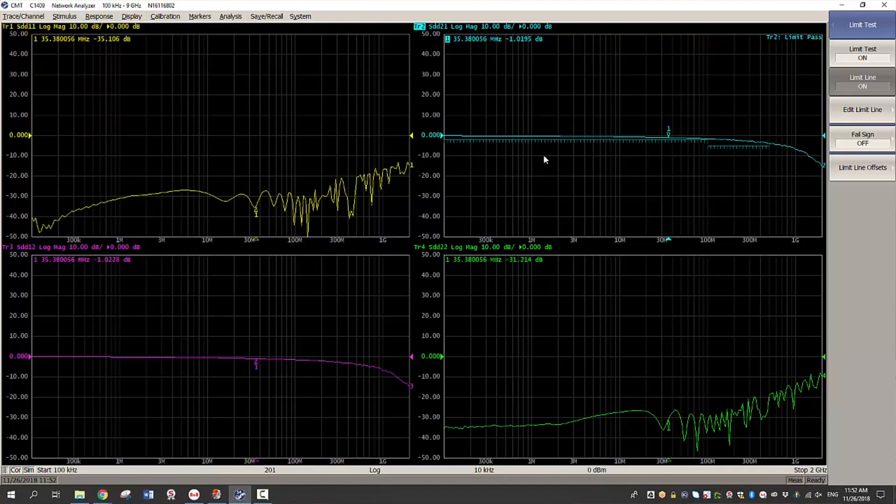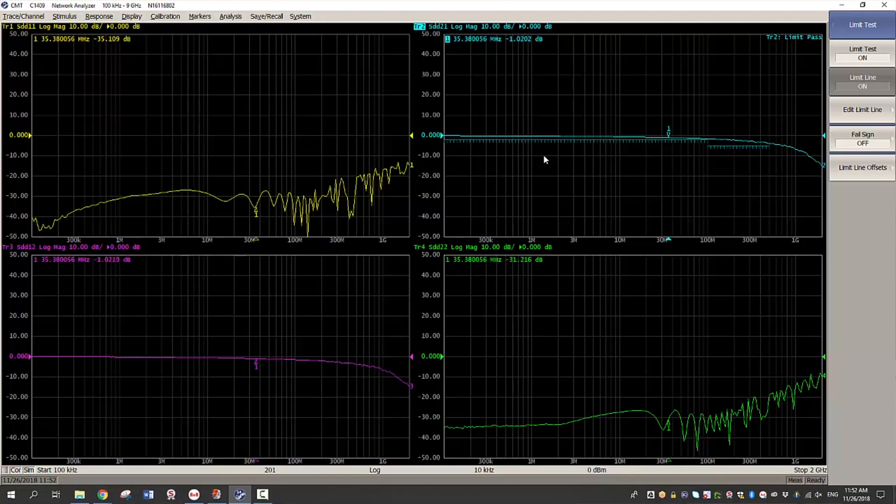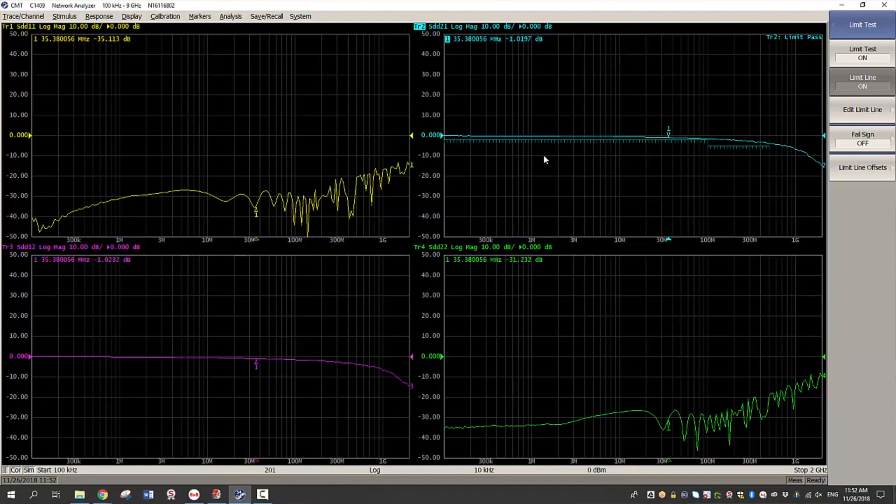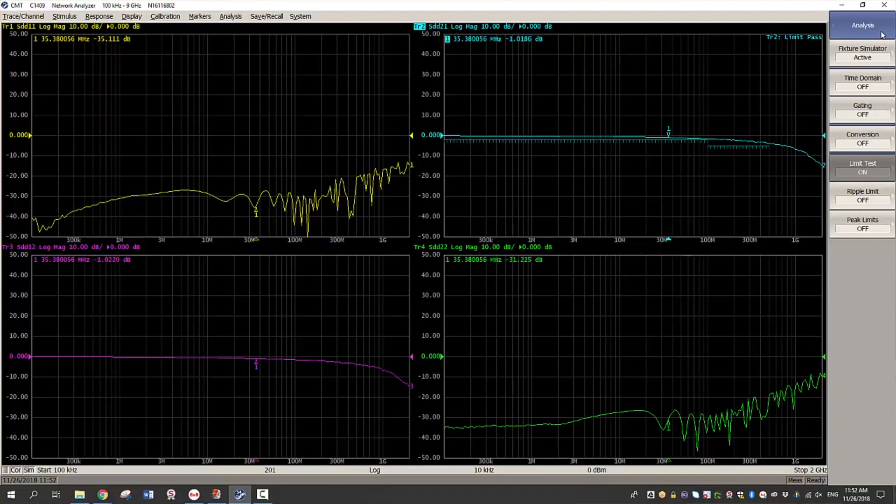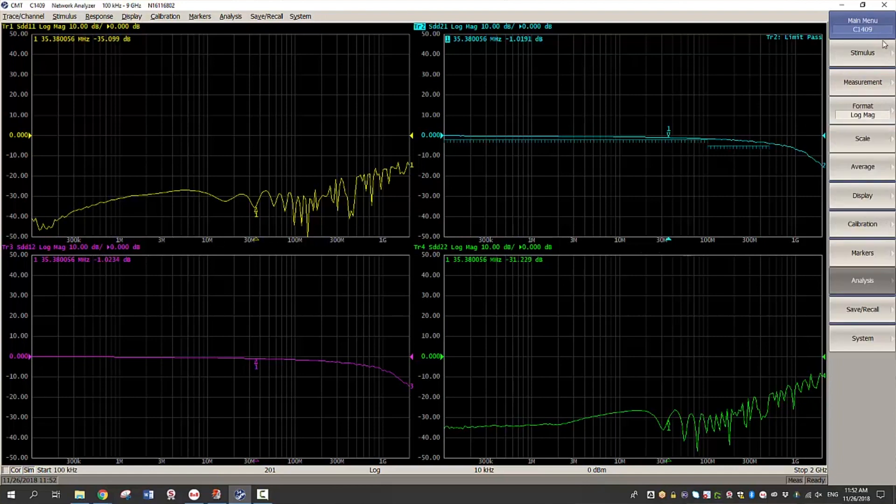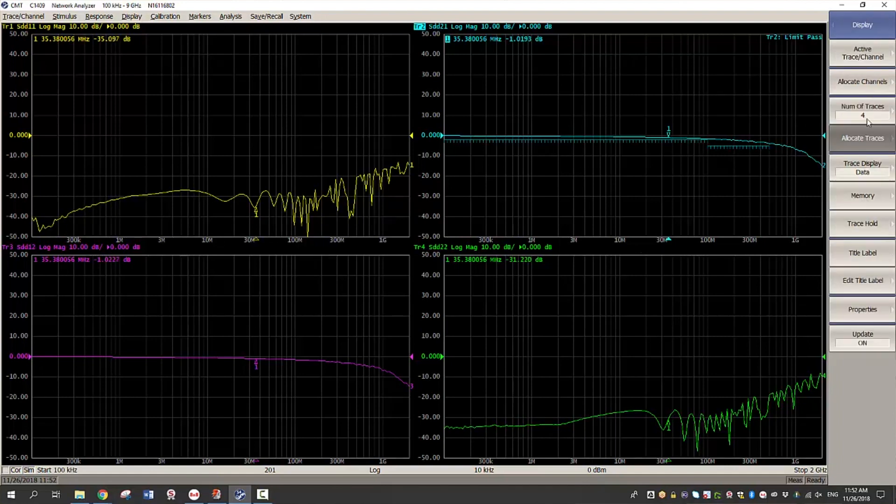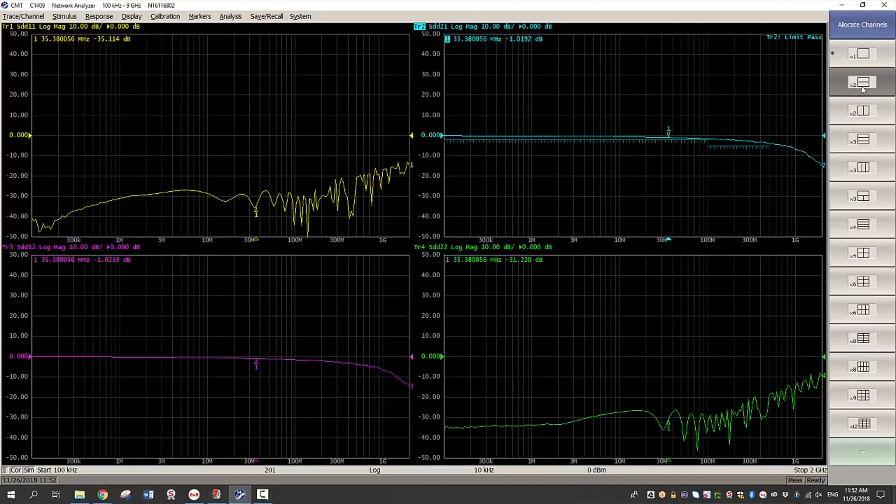Another important feature of a VNA is its ability to measure time domain measurements. Time domain measurements is especially intuitive because it helps the user see impedance versus distance and it's especially useful to identify faults along the cable. So let us begin with the time domain measurements by adding a second channel.